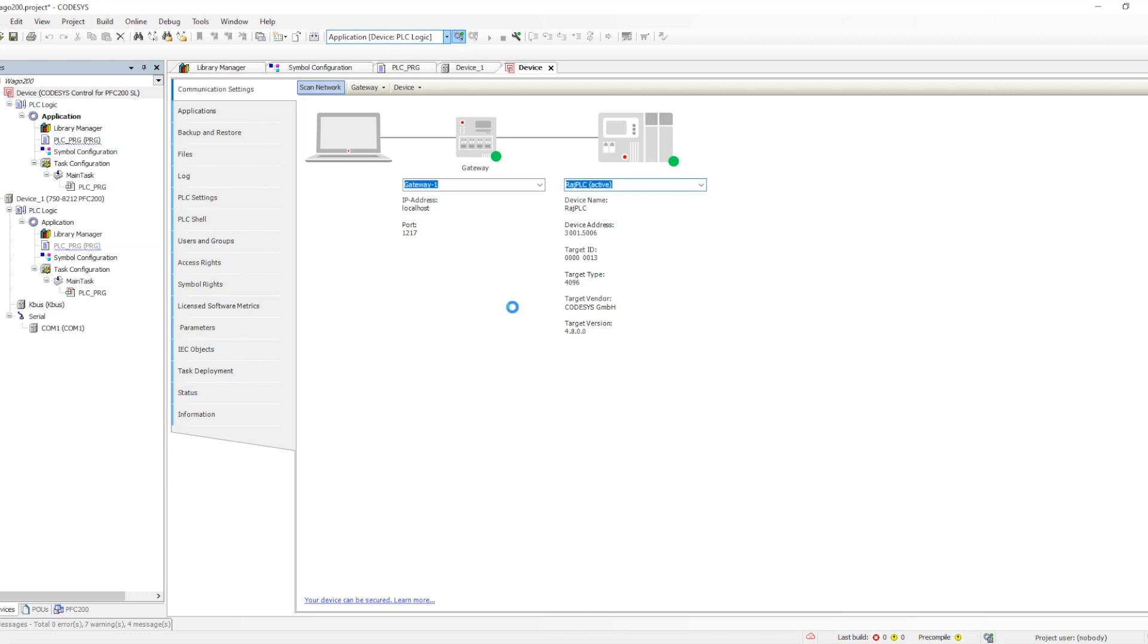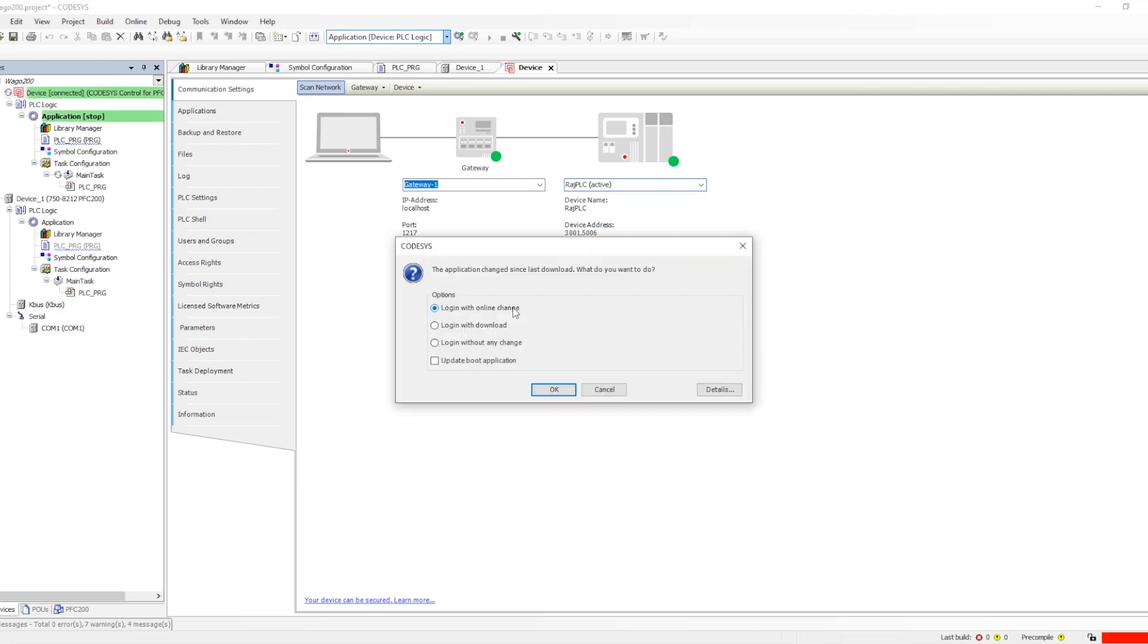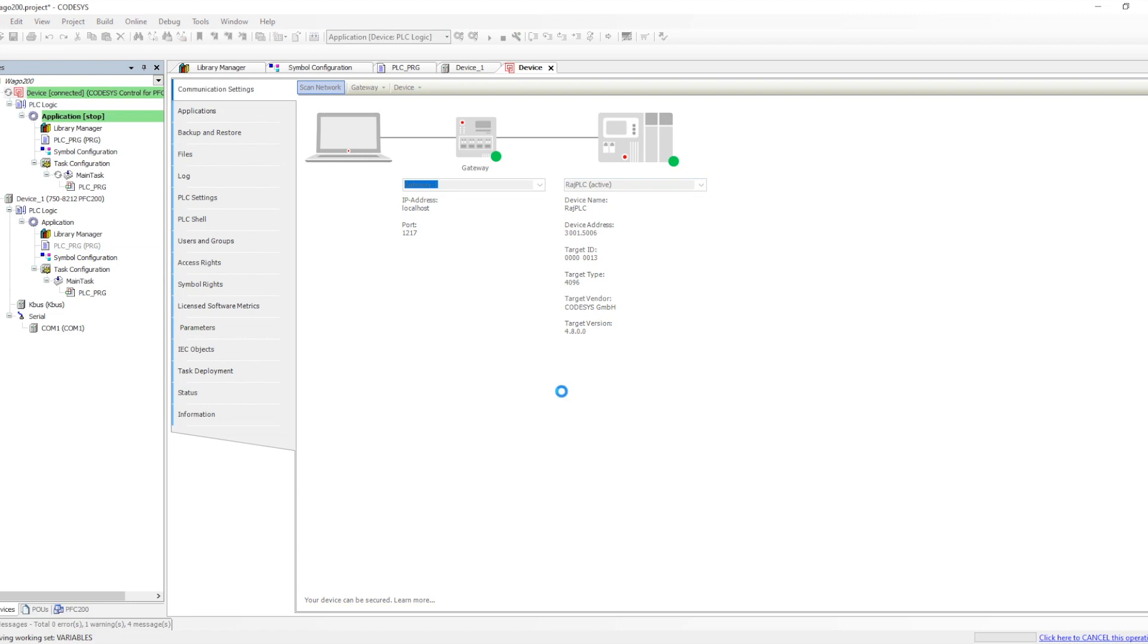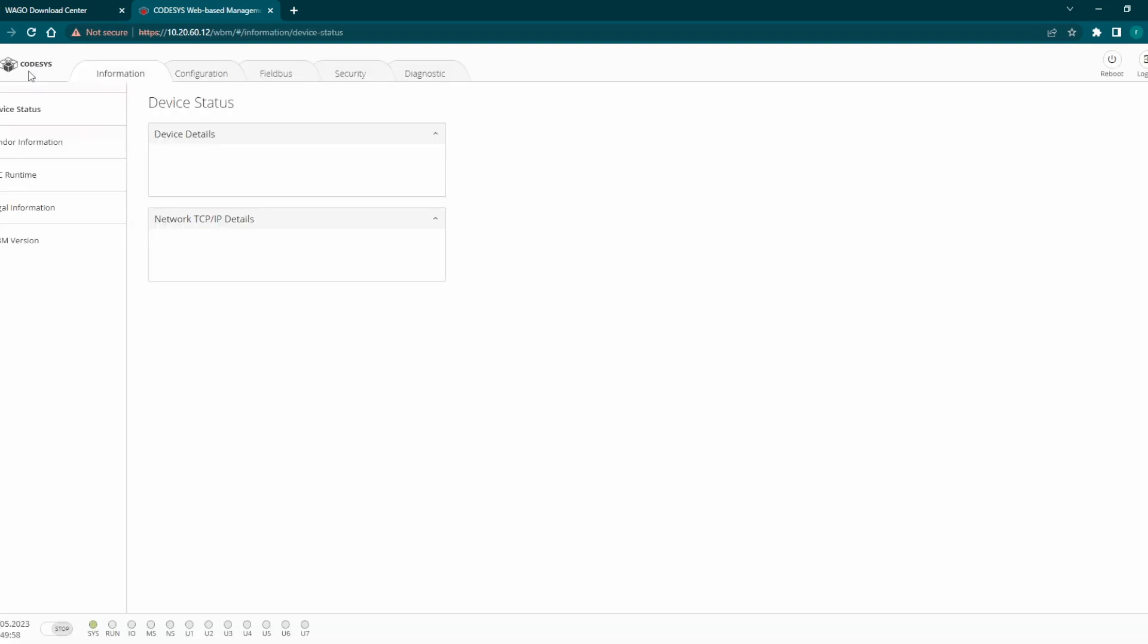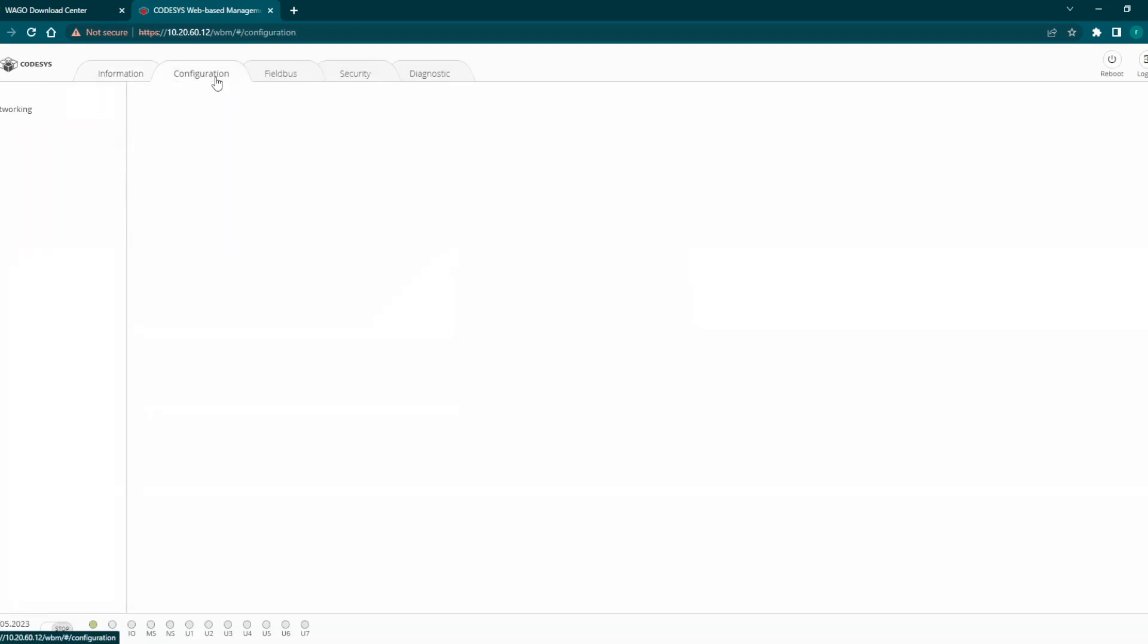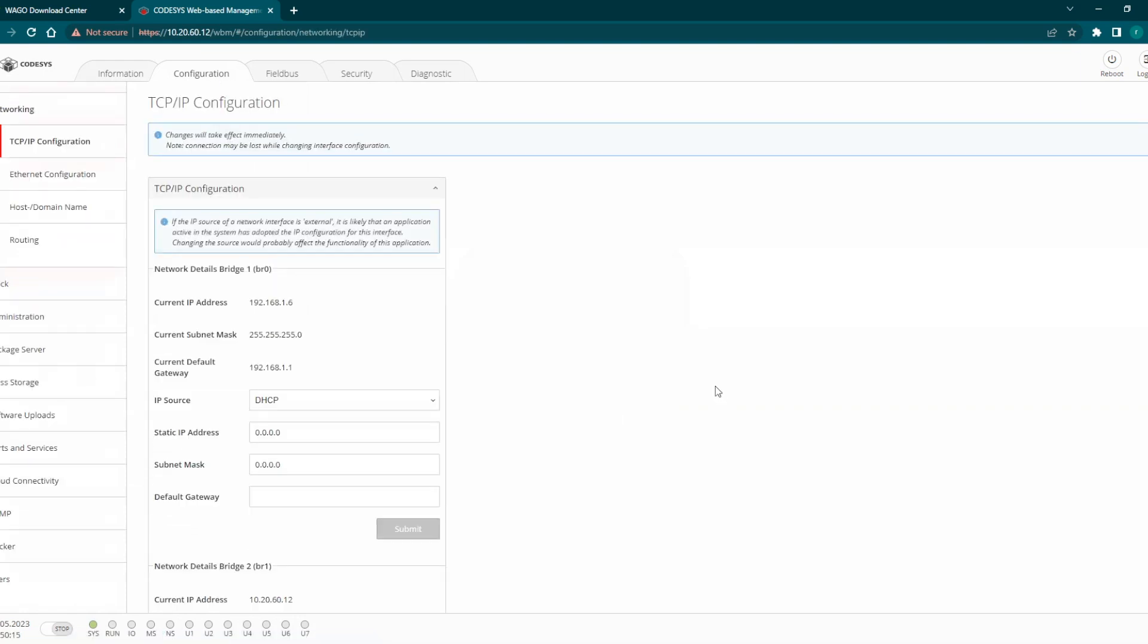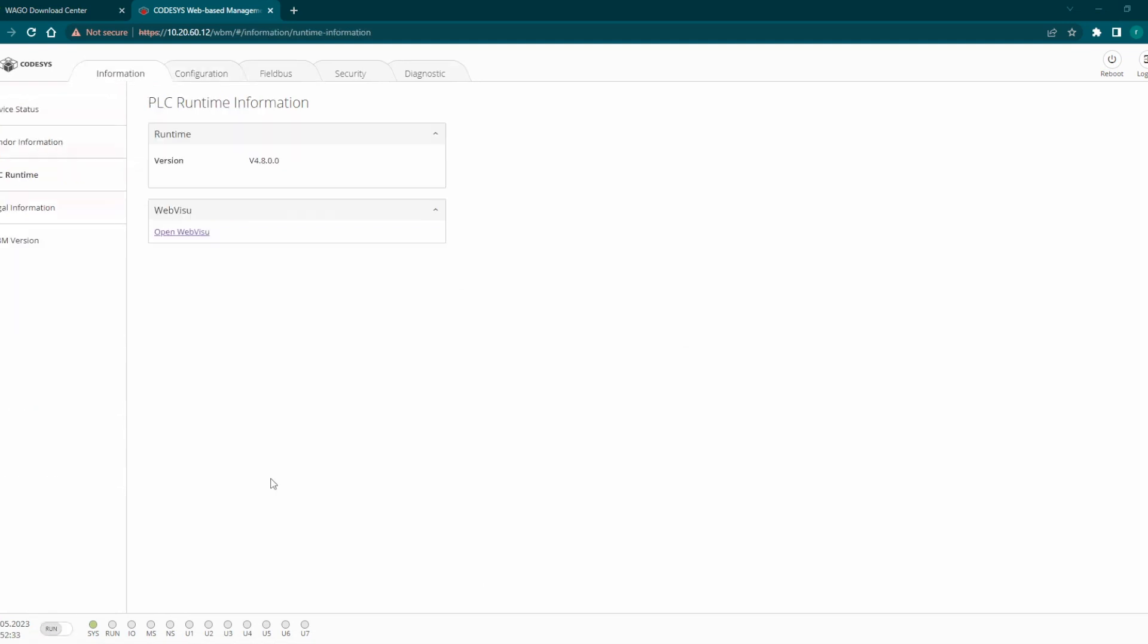For the device it was coming as 6.1 and it was named as device for the WAGO. But here it is 4.8 and the target vendor is Codesys. This is how it changed. When we login to the web browser it will also get updated with the Codesys icon instead of WAGO. You will not see the option to select between Codesys v3 and none. By default it will be showing in the PLC runtime as the runtime which we have installed, which is 4.8.